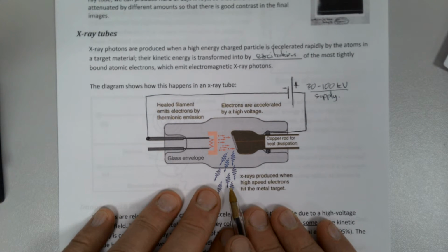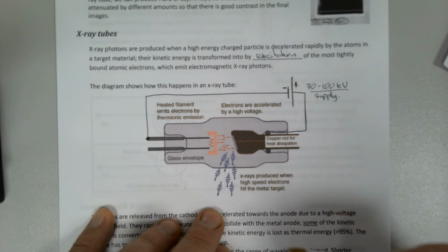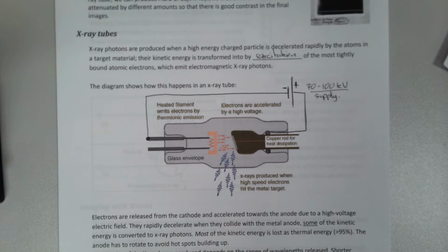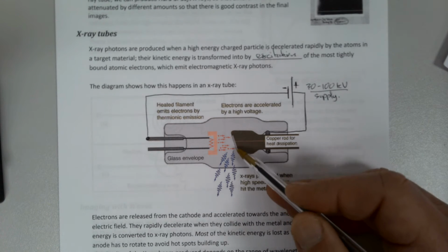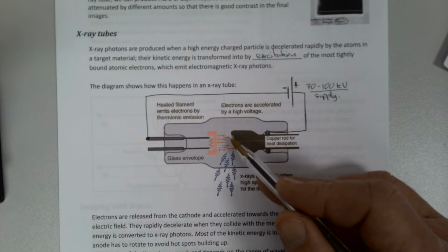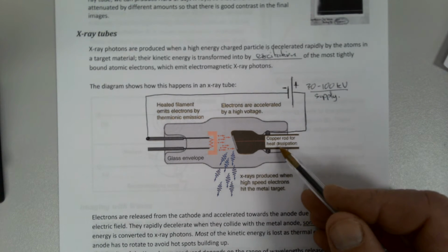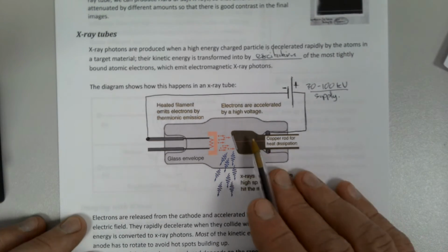Not all of them will be X-rays. An awful lot of them will fall down in smaller steps within the atom, and so what we get is lower frequencies. Infrared, an awful lot of energy is deposited as heat, so our target, which has to be quite tough to take the impacts, will be something like tungsten, but we'll embed it in copper. So a very large mass of copper, good thermal conductivity, big mass, temperature rises are going to be lower, etc., and then take that away.